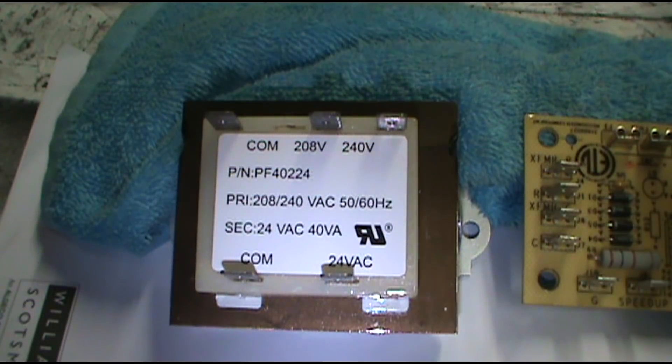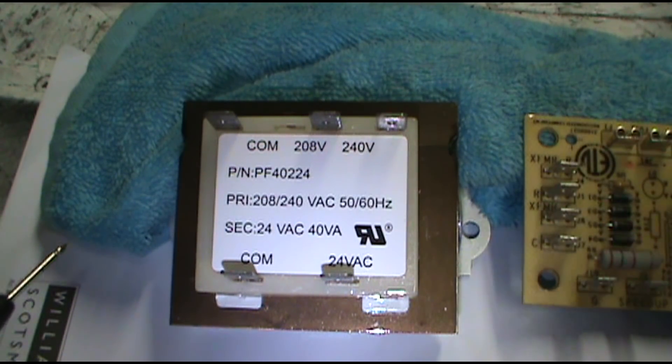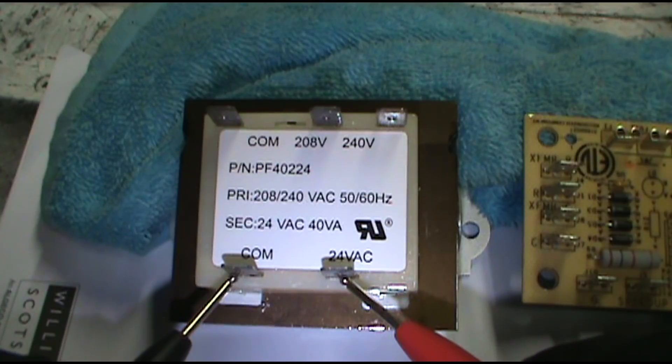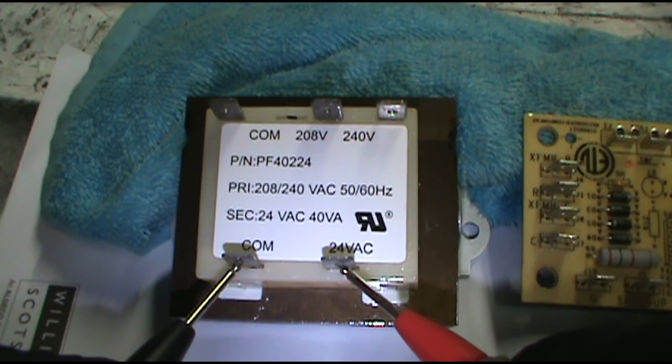All right, let's say you're not getting any low voltage anywhere, no low voltage. First thing I would do is set my meter to AC voltage and touch between 24 volt and common. And if you've got no 24 volts here, you got a bad transformer. You need to replace it.